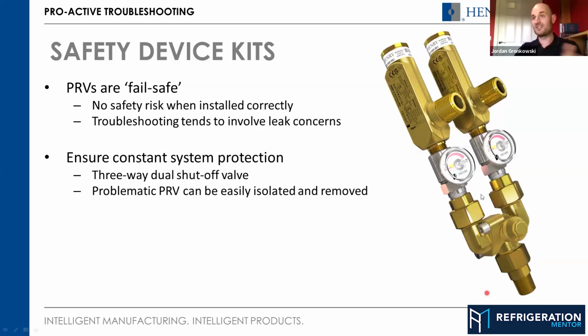The advantage of this is that if you have a problematic valve, or even if a valve just blows because you've had an issue, you can switch this valve across and isolate the problematic one. In this case, it's a cap you remove, and you put a little spanner in, and you can change the flow from this angle to this angle. That allows you to remove the isolated valve without any depressurization of your system, any degassing, anything. You just pop the valve off and away.